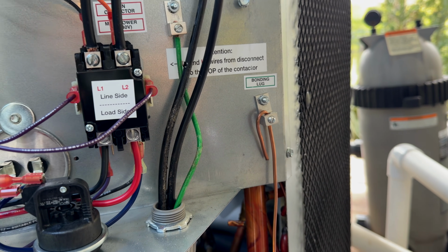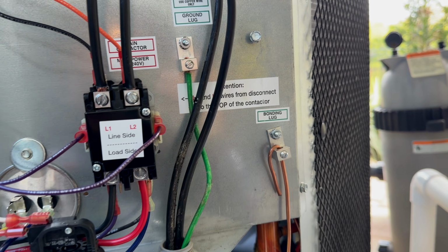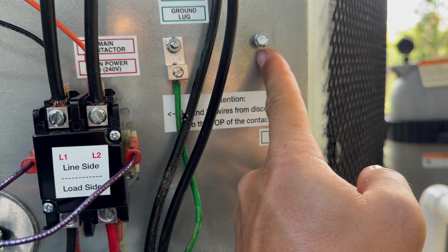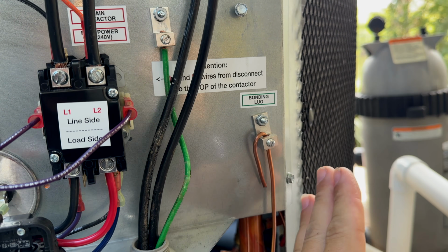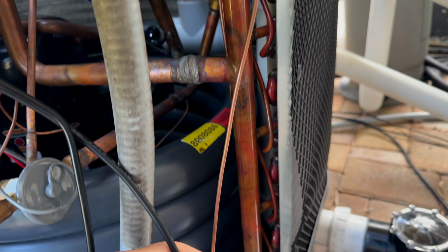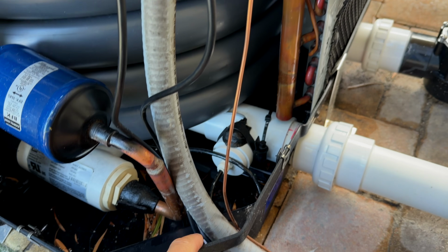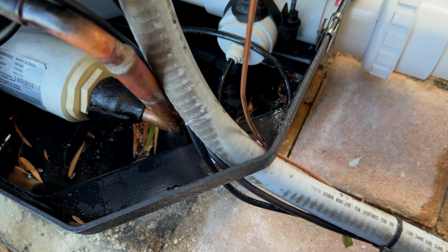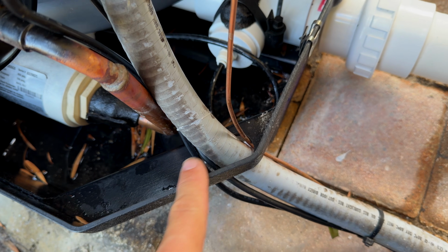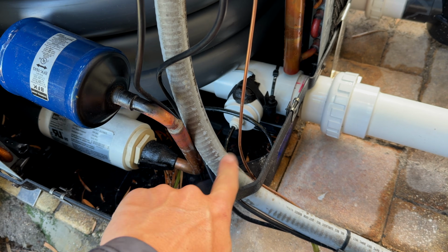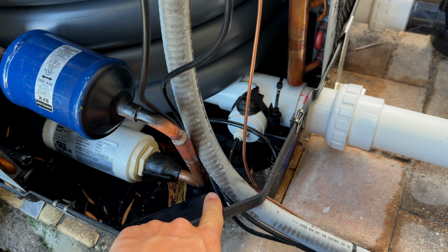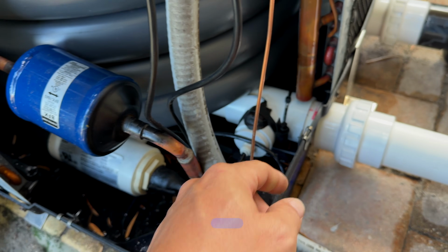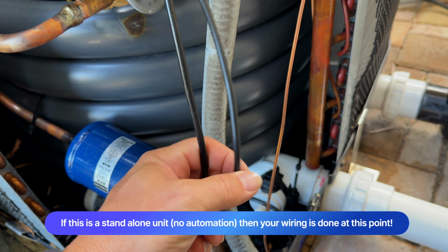And then this is the bonding lug, so this is not enclosed in the electrical box when it is closed. You can see the bolt for the doors here, so it's off to the side, and it's run down through the same hole the conduit's in. One nice thing Gulfstream does is leave an ample size hole here in the cabinet for you to run the 3/4 inch conduit, the bonding wire, and in this case 2 communication wires.